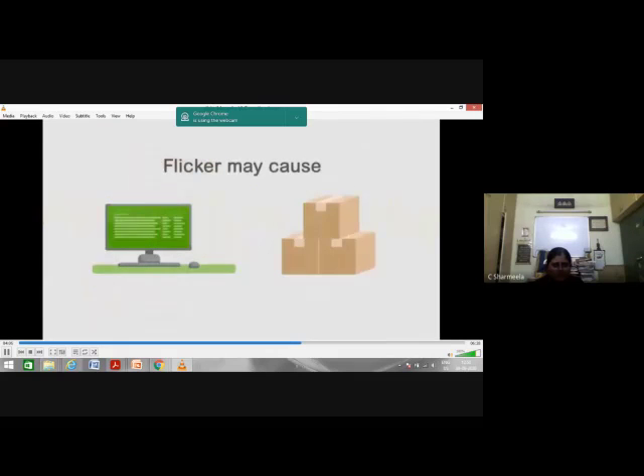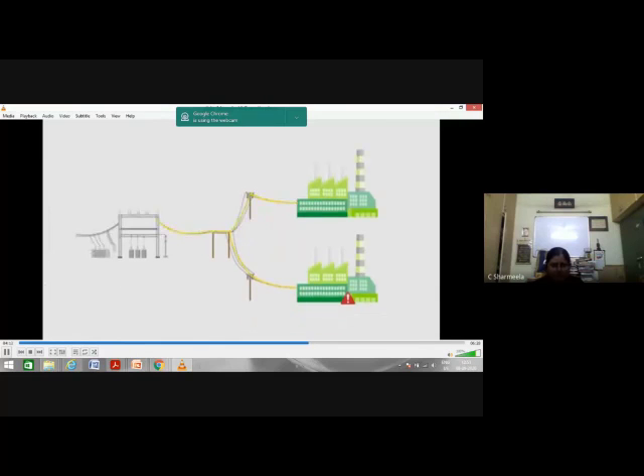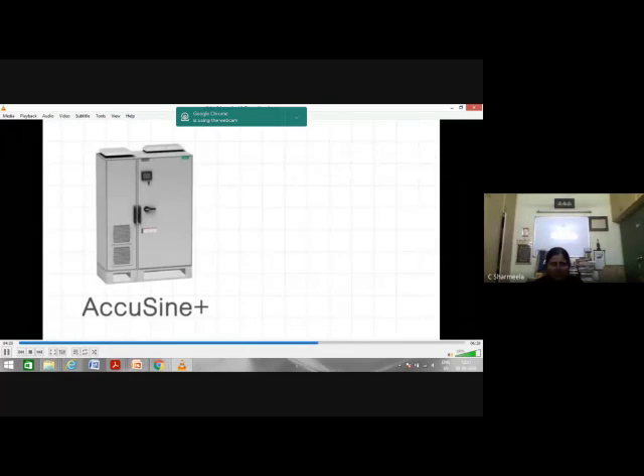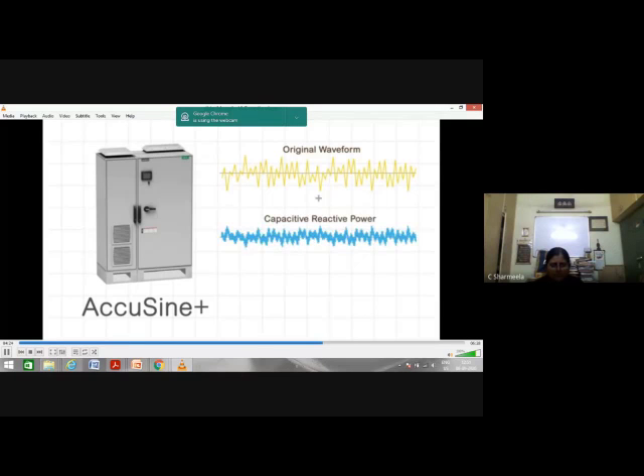Flicker may cause process downtime or generate poor quality products. Furthermore, utility companies may force the consumer to mitigate flicker if they're creating power quality problems on the utility distribution line. To solve flicker, the AccuSine PLUS in power factor mode can be used to inject capacitive reactive power to counteract the inductive reactive power demanded.